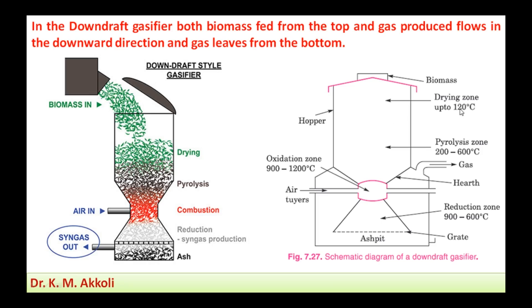The drying zone has a temperature up to 120 degrees Celsius. The pyrolysis zone has a temperature range between 200 to 600 degrees Celsius. The oxidation zone has a temperature of 900 to 1200 degrees Celsius, and the reduction zone has a temperature of 900 to 600 degrees Celsius.